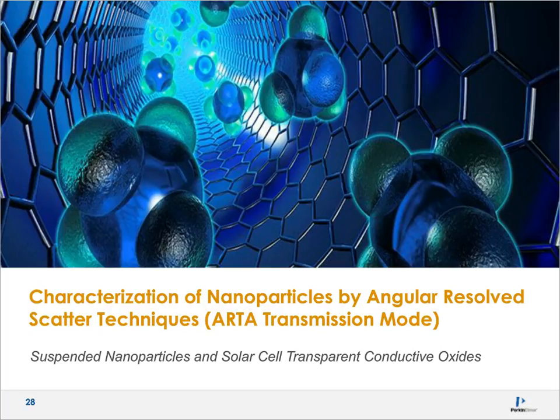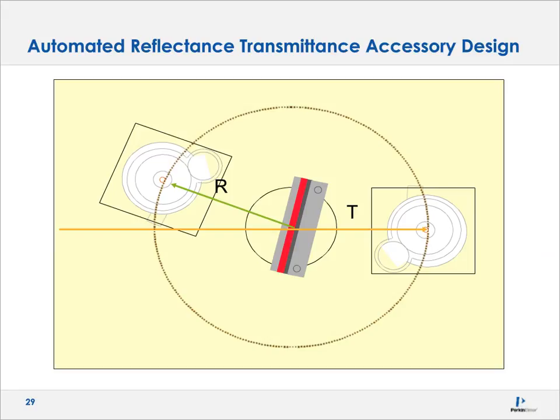We're now moving to characterization of nanoparticles by angular resolve scattering techniques, involving an accessory called an ARTA — automated reflectance transmission accessory. We'll first look at suspended nanoparticles and then solid nanoparticles, specifically solar cell transparent conductive oxides. The ARTA has a movable integrating sphere detector able to move around the sample in 360 degrees. The sample itself on the center stage can also move through 360 degrees. We can change the angle of incidence by rotating the center table, or change the collection angle, with configurations for both transmission and reflectance modes.